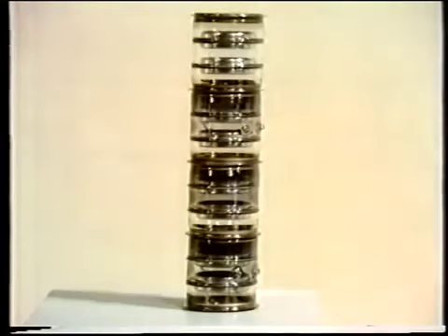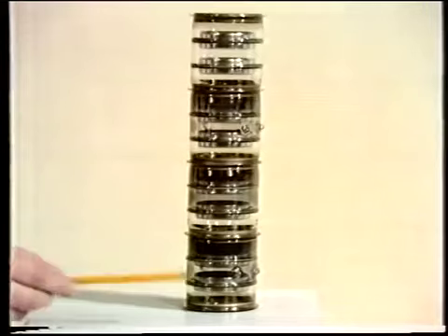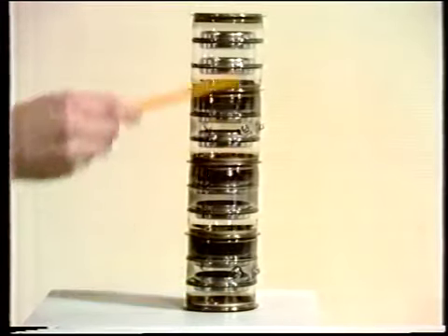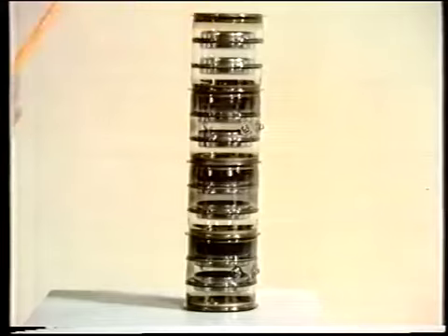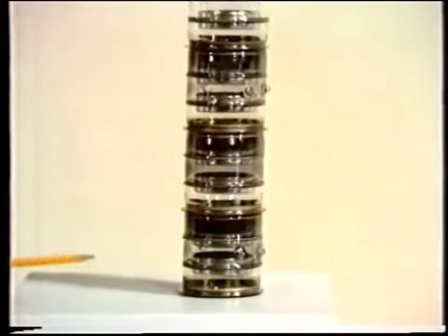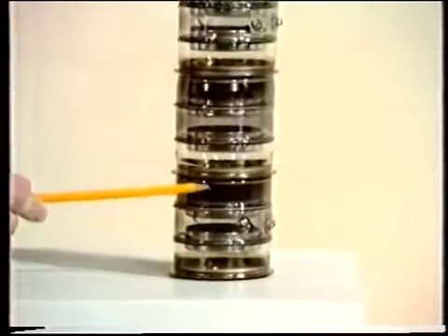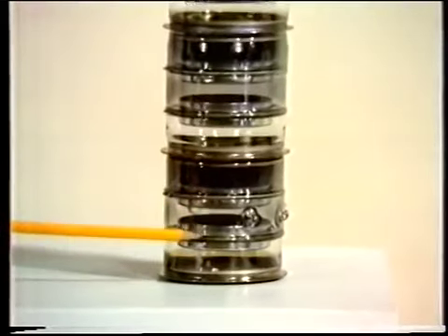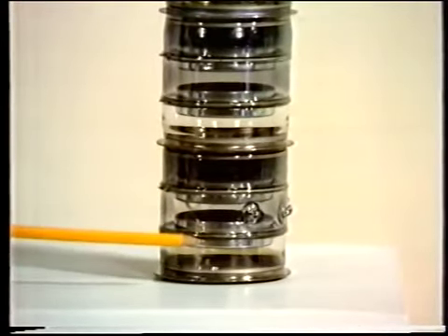Well, now, the whole of this unit will be put inside a solenoid that provides the focusing field to keep everything in focus. Well, it's a little bit hard to see what's going on here. It's been encapsulated to keep people away from the high voltages. And here is a tube without the encapsulation. It's the 4-stage tube. Down here we have the photocathode, and up here the output phosphor. It's, as I say, made up of 4 stages. Here's the first stage here. You see a couple of rings in here. These, in fact, are electrodes to which the high voltage is applied.